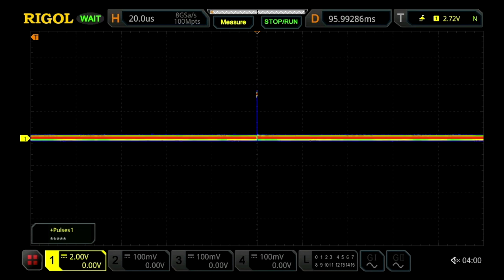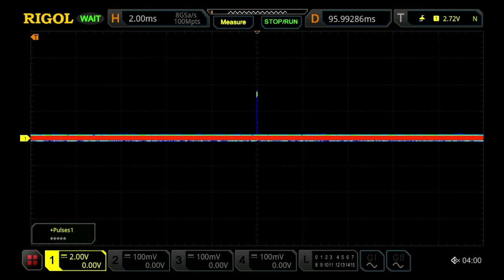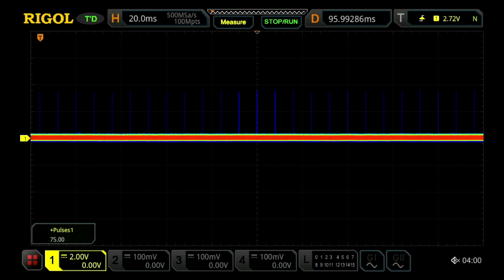We go out to the same 20 milliseconds per division. We now see the whole series of 25 pulses and we're accurately measuring 75. This is because with 100 million point memory depth and the precision measurement mode, we can clearly capture all 75 pulses. That's 25 sets of the triple pulse.